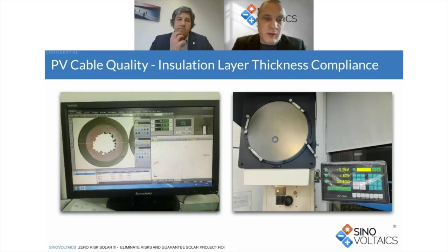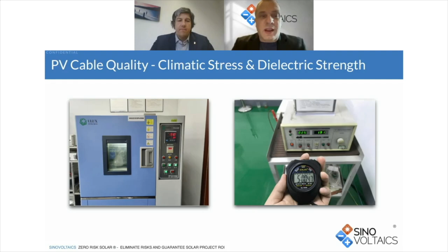Then there are other important tests that I'd like to quickly introduce here. One is the dielectric test, to confirm that the cable meets certain minimum electric strength values and can endure high voltages without breakdown. Also, climatic stress tests involving low and high temperature and humidity stress tests in specific cable climate chambers are used to cross-validate the physical and performance properties of mass-produced cables according to the applicable design requirements.